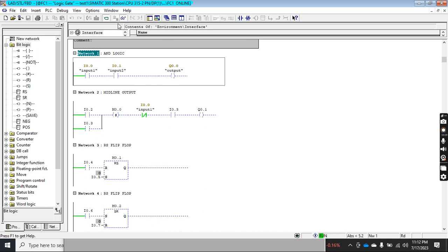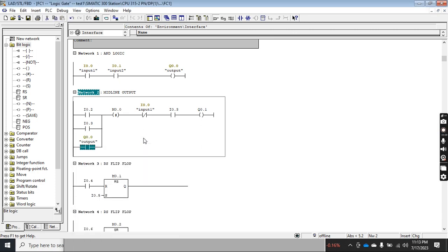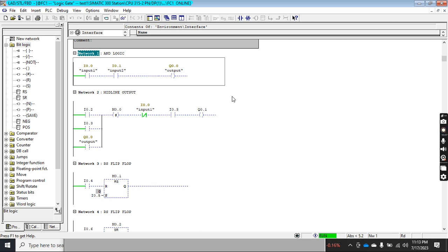You can use an output address as an input. For example, I write address Q0.0 — which is the output of one network — as an input contact in another network. After saving and downloading, it will accept it. The key rule is: output Q0.0 here is used as an input contact, not as an output, so the output assignment must be unique, otherwise you will get an error.